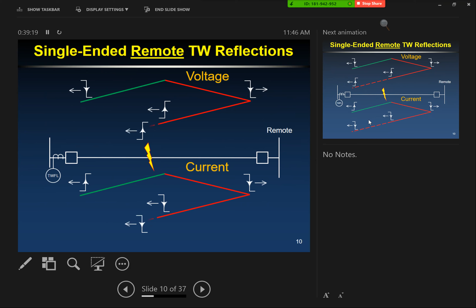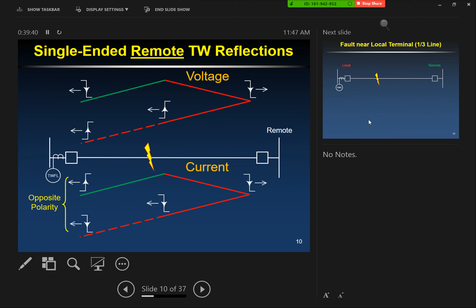There's never a polarity change when you're just passing through an impedance like that, only when you're looking at reflections. And so that returns back to the remote end. The takeaway here is opposite polarity for remote reflections, while local reflections were the same polarity, and we're just focusing on current here. This will help us when we're looking at events later on. Do you guys have any questions so far?